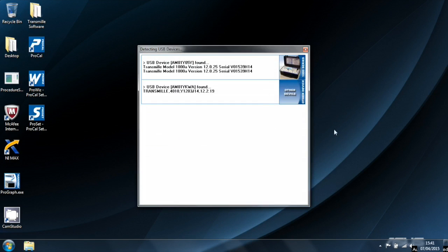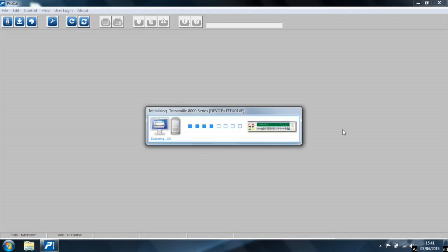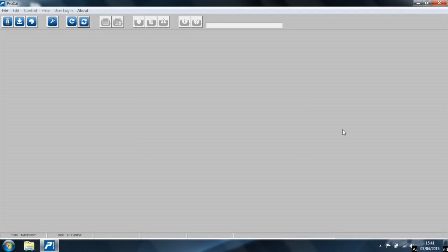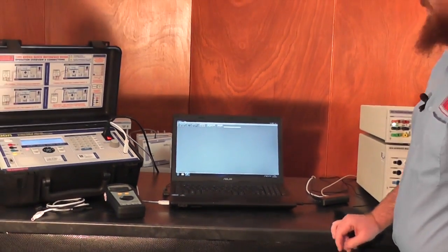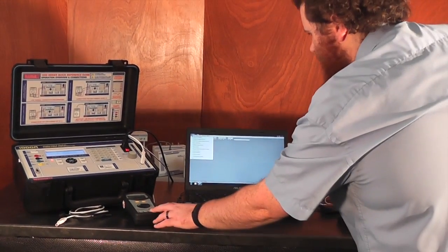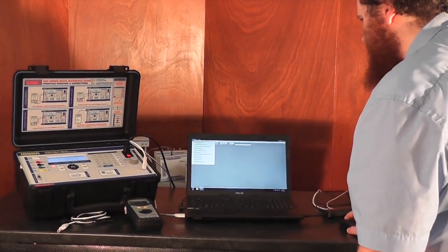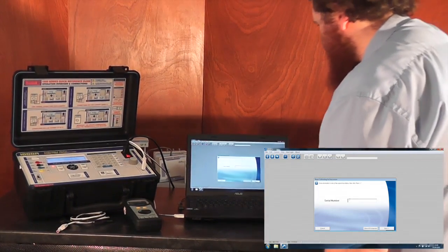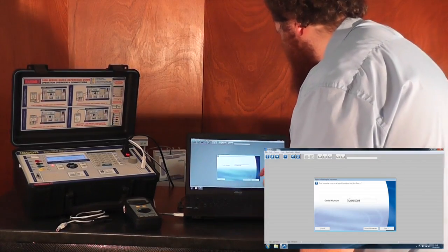So when we run ProCal, we will see the list of instruments that it has detected on the USB interface, and it will continue to start up, automatically initializing the multimeter and the 1000 series connected to the computer. Now that we have configured ProCal using the ProWiz software, we will continue and proceed with making a calibration on this multimeter.